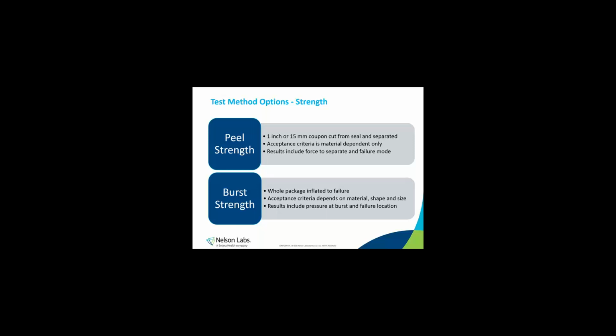If you run a burst test, the whole package is filled with air and pressurized until it bursts. Burst acceptance criteria is dependent on material and size, and to a degree, the shape of the package. So each package may need a different specification, depending on how great that burst pressure difference is. Now, let's look at a video with some examples of seal peel testing.